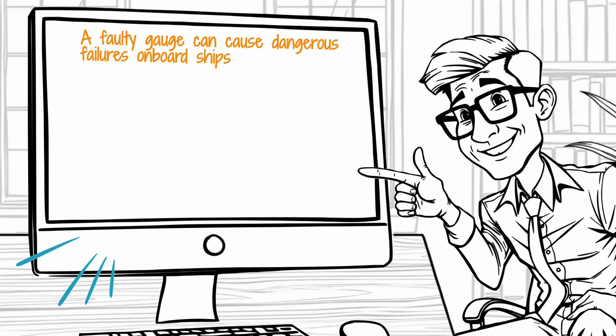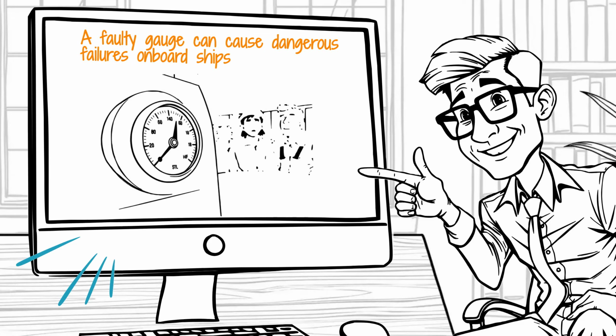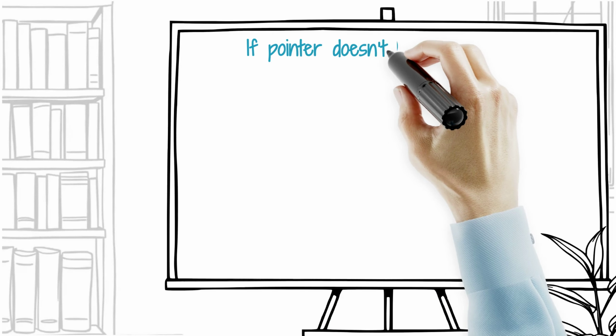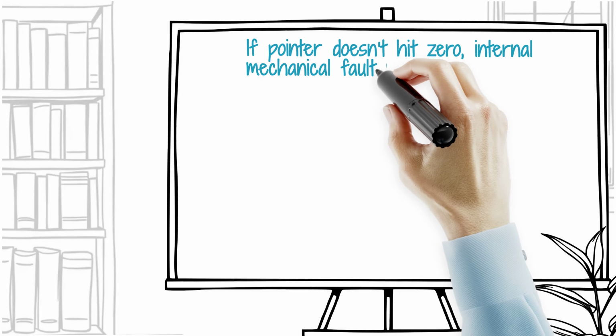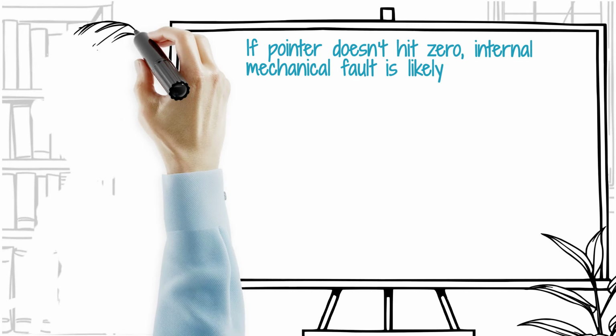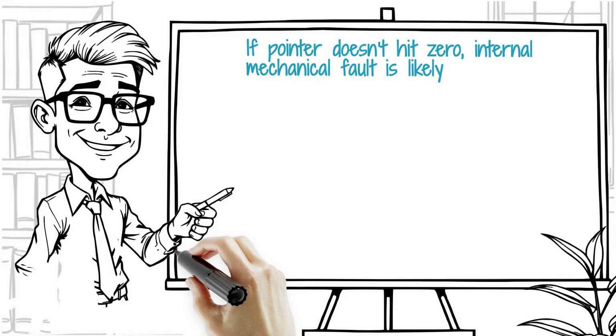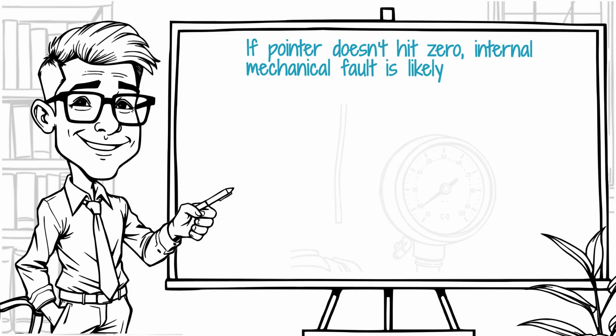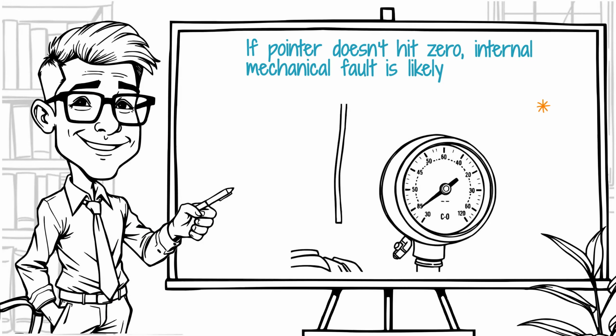Slowly bleed the pressure to ensure the pointer returns to the zero mark. If the pointer remains slightly above zero, it usually indicates a mechanical shift in the internal linkage or a deformed Bourdon tube. Carefully remove the gauge and clean the external casing to inspect for any cracks in the glass or signs of corrosion on the brass socket.